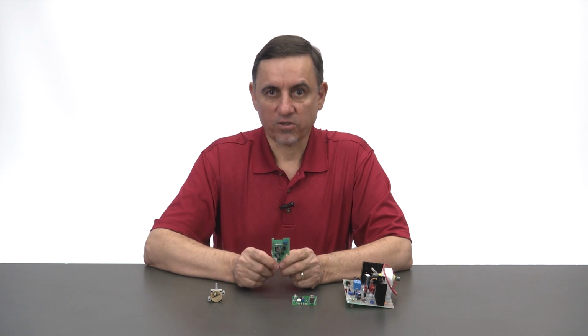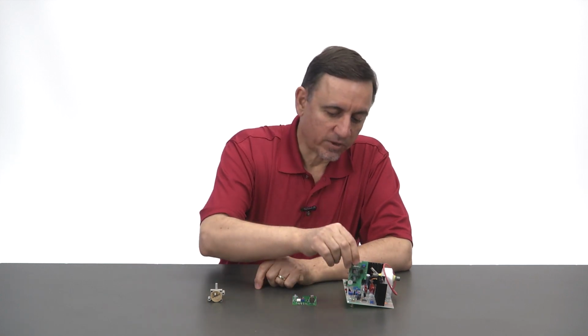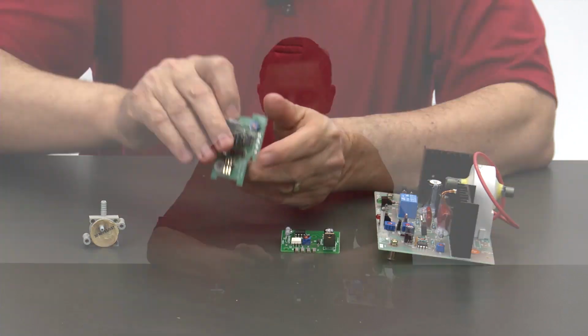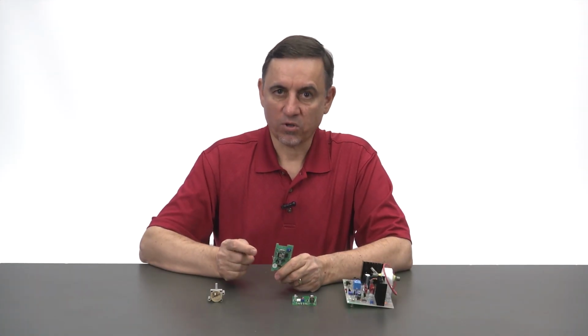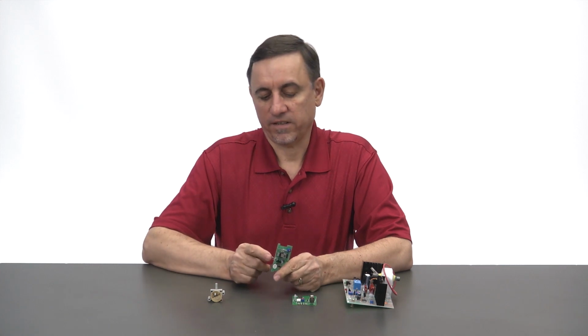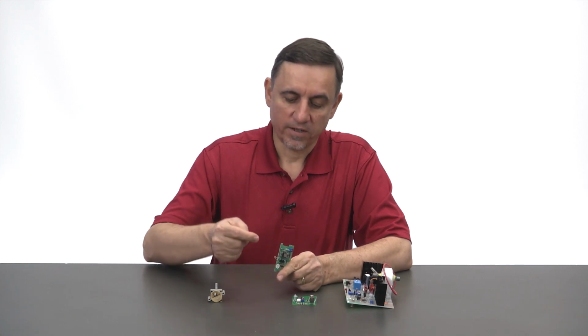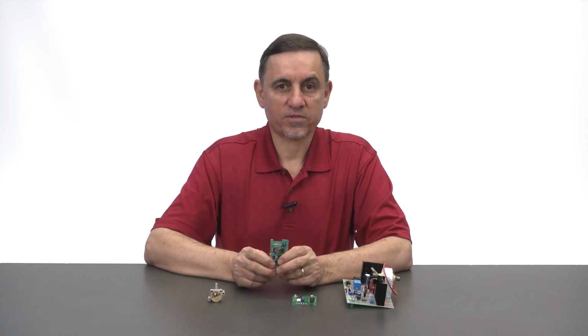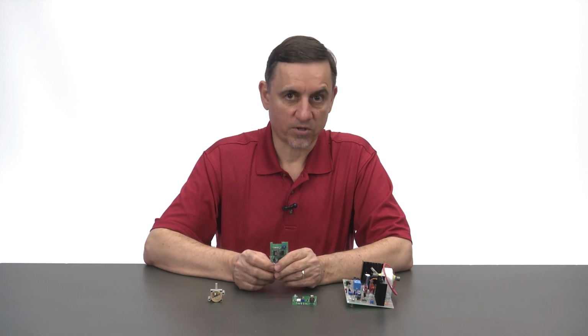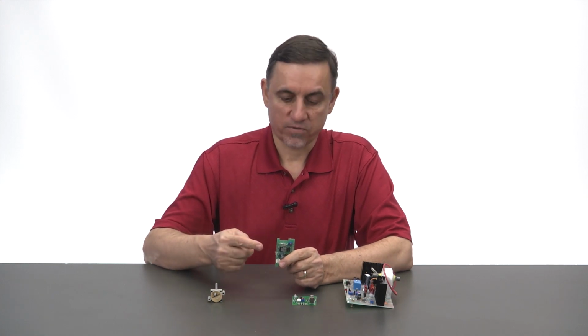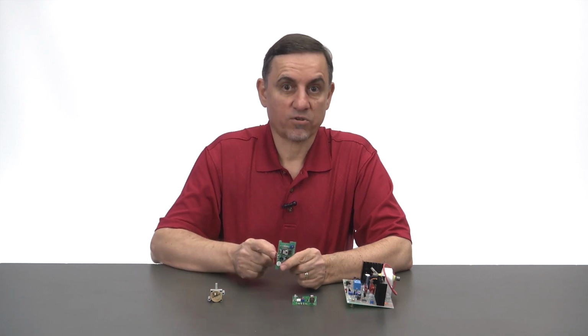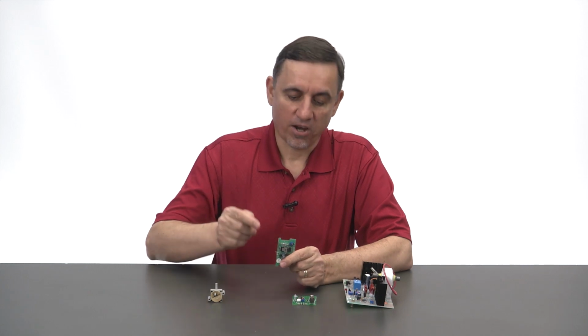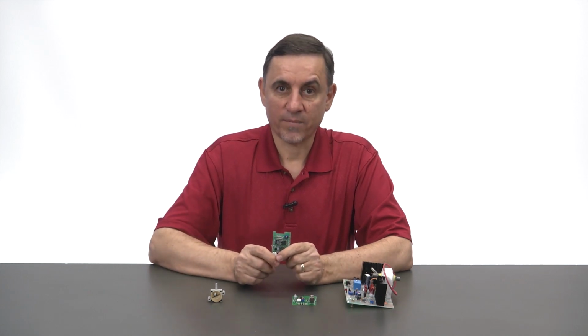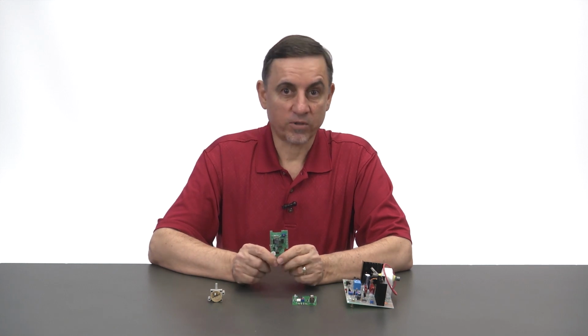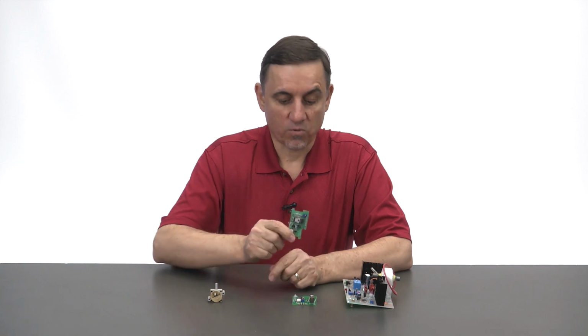So the way this is installed in the unit, again, this one's obsolete, but it kind of plugged into a circuit board similar to this one, and it kind of looked like this, where it was plugged in. And on the side of the air cleaner cabinet, there was a very small hole, about 1/4 inch round, and it was right opposite this little probe here, the sensor probe. So the sensor probe got hot, the air cleaner said, hey, I'm good, turns itself off. When the furnace blower comes on, air is drawn from the furnace room through that small hole, blows across the sensor, cools the sensor off. The sensor then says, hey, there's air being sucked into the air cleaner cabinet. That means the furnace blower is on, so I'm going to turn on the air cleaner. So that's how all of these work.